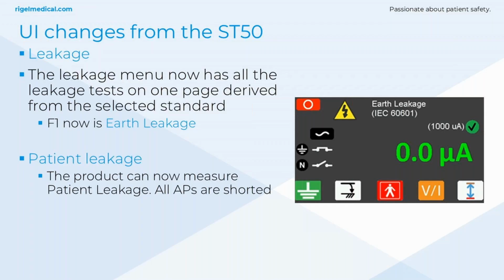It can perform the test with all the applied parts shorted, perfect for NFPA 99. That will really help streamline your process. And again, you can stack the leads so you can have multiple ECG or applied part connections to the safety analyzer. For NFPA 99, obviously the step for CF is irrelevant. You've still got the testing for NFPA, where it just groups all the tests together, and it's efficient for whatever you need for doing that. So it's very little hassle when it comes to testing to NFPA 99.